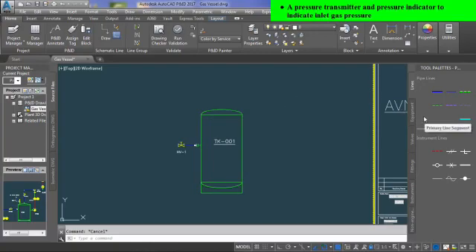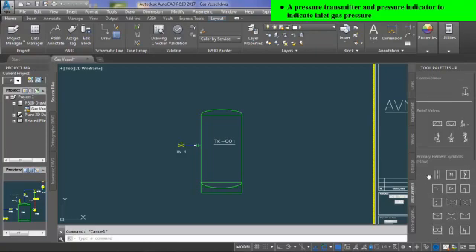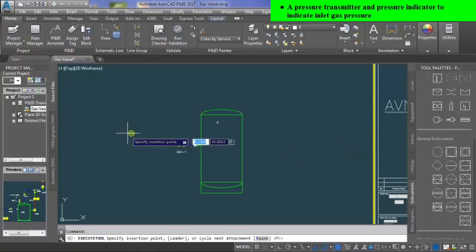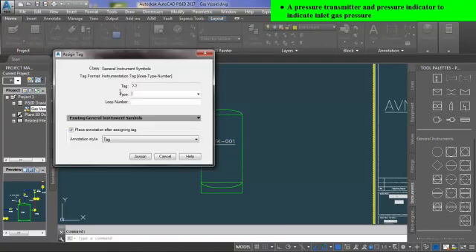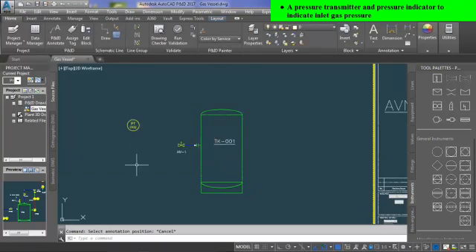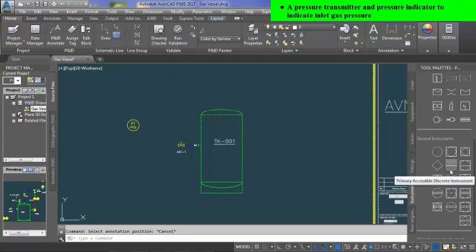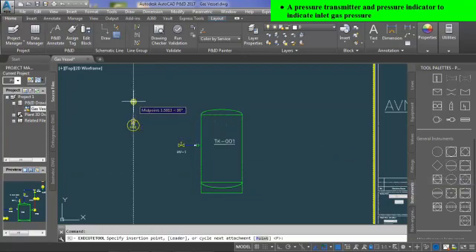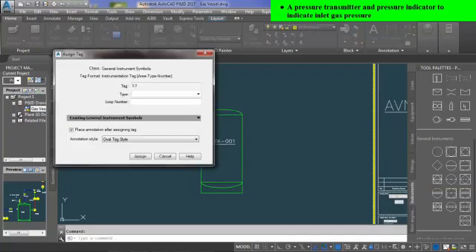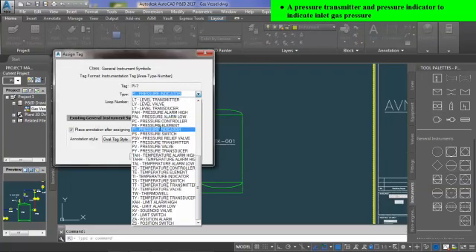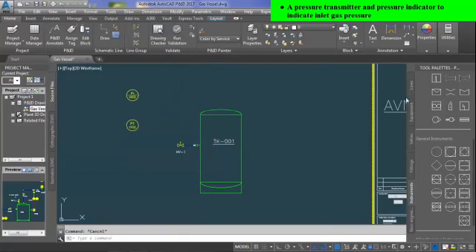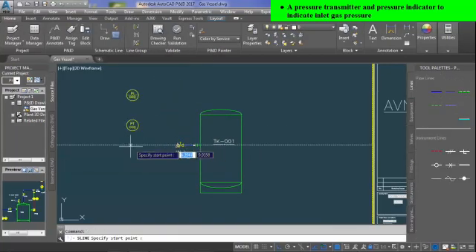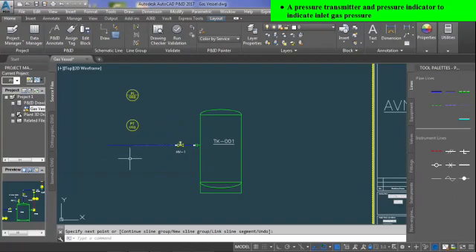Now the next instruments on the list are pressure transmitter and pressure indicator to monitor the gas pressure of the inlet pipeline. For that, go into the instrument tab and select field discrete instrument, or in other words, field mounted. It is a pressure transmitter, so assign it PT-2 tag. For indication, we have to add a pressure indicator from the instrument tab, which is primary accessible discrete instrument, or in other words, panel mounted instrument. Assign it a tag of PI-2. As pressure indicator and pressure transmitter are both in the same loop, the loop number is the same.